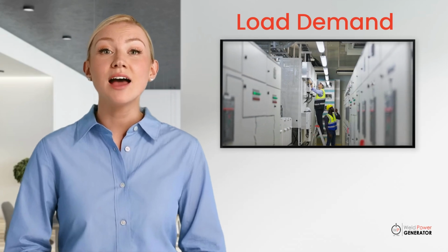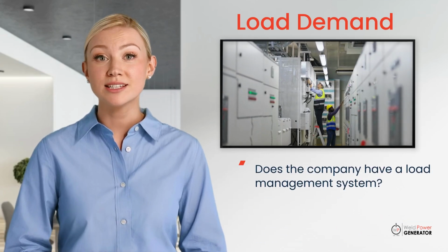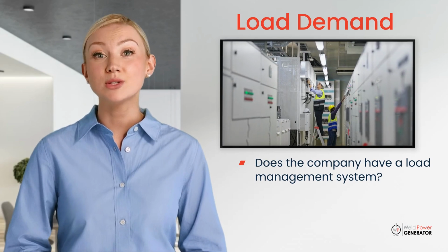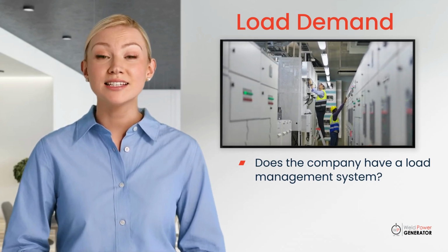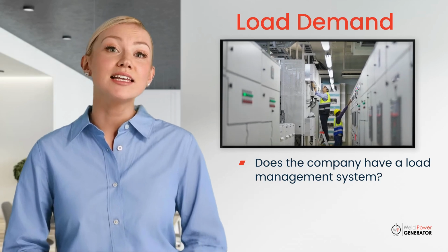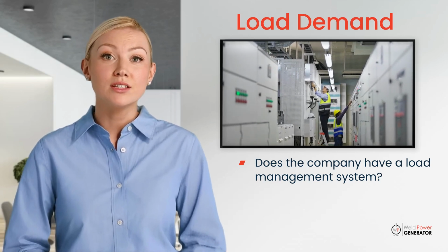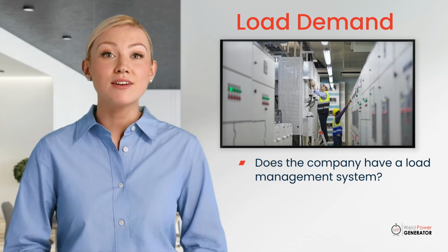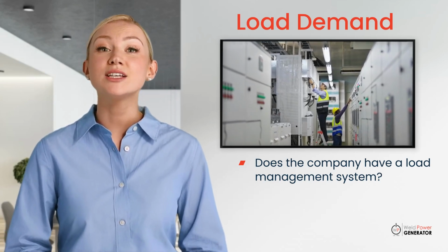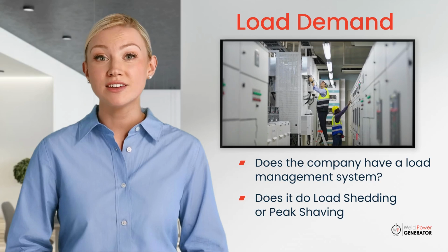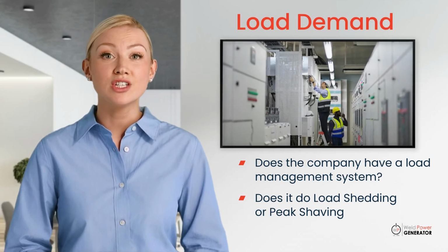Certain facilities with high power demands use load management systems to supplement power during peak usage periods. In these cases, the generator may be programmed to run even when utility power is available to balance electrical loads and prevent demand spikes. If your facility uses a load shedding or peak shaving system, the generator's activation could be intentional.